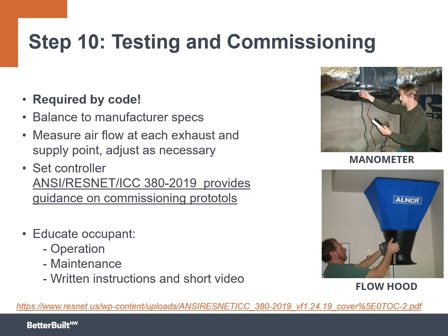On top of all this, we also need to educate the occupant. The occupant needs to understand how the system is designed to operate. They need to know what maintenance will be required, and it's ideal if they have a set of written instructions or a short video available. Think not just about the first homeowner, but if the average amount of time people spend in a home is 7 years, and a heat recovery ventilator is designed to last 25 or 30 years, then there could be a second or third homeowner down the road who also needs this information. So it goes beyond just explaining to them in person. Giving them a written set of instructions or a digital way to understand this, such as a short video, is really ideal. So testing, commissioning, leading towards homeowner education, required by code, and this is maybe the most challenging part that we've seen people be able to do repeatedly. The more often you do this, the easier it will become.